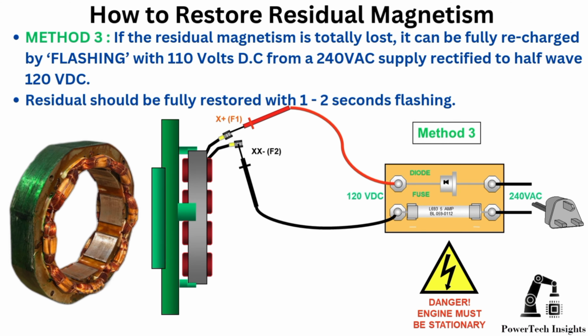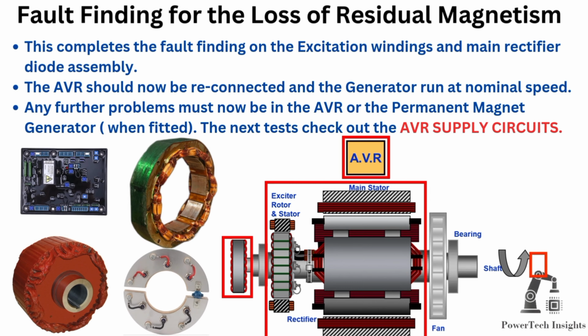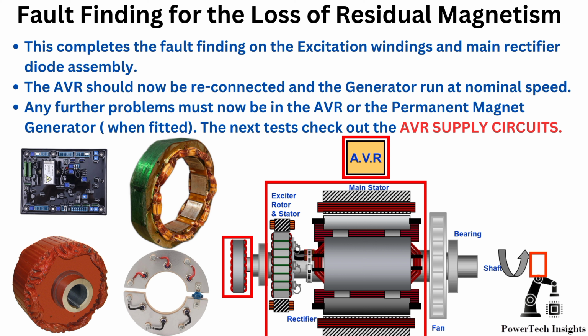Method 3. If the residual magnetism is totally lost, it can be fully recharged by flashing with 110 volts DC from a 240 VAC supply rectified to half-wave 120V DC. Residual should be fully restored with 1 to 2 seconds flashing. This completes the fault finding on the excitation windings and main rectifier diode assembly.